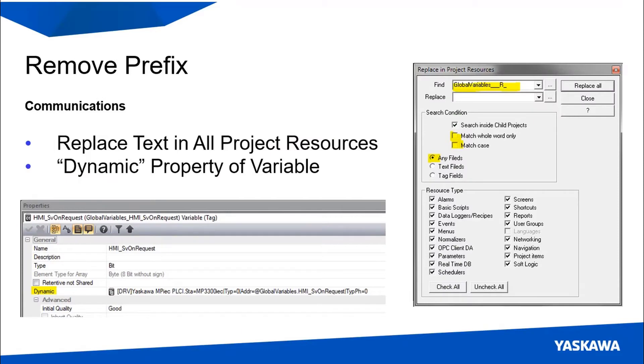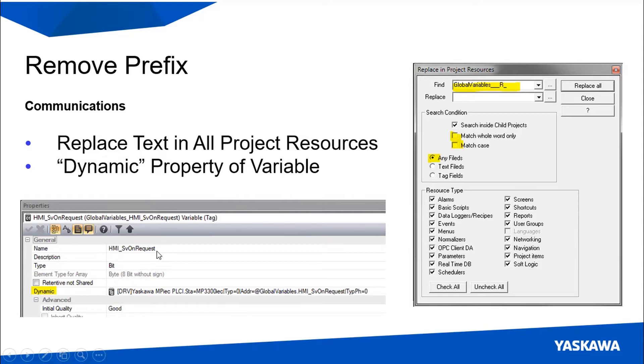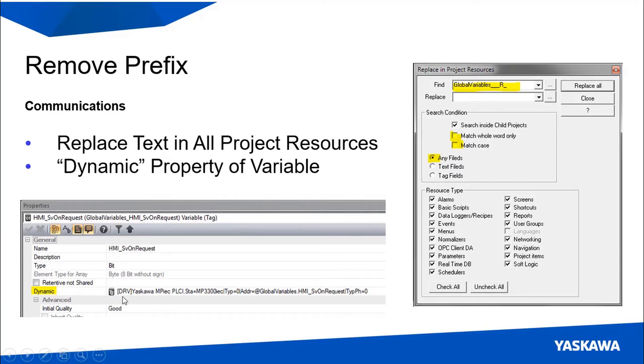When you have the variables we would like you to shorten the names of those variables by using this replace text in all project resources tool. It's basically find and replace, you'll find the prefix and replace it with nothing and that will shorten up the names make them a lot easier to read. The reason you can do this is it's not the name that's really all that important for communications over PLCI, instead it's the dynamic field property of the variable as you can see here is very specific.